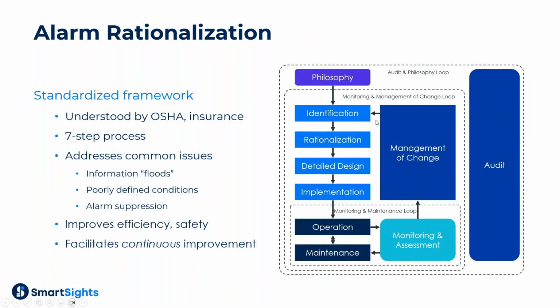That will inform basically our management of change. The operators are getting flooded with all kinds of alarms. We need to go and change some of these conditions here because this really isn't working. And the problem is, in many plants, you have thousands and thousands of alarm conditions, so you can't simply pour over every one of those and reevaluate it all the time on a continuous basis. It requires statistical analysis to do this monitoring and assessment piece.